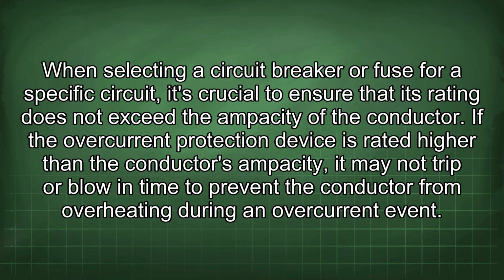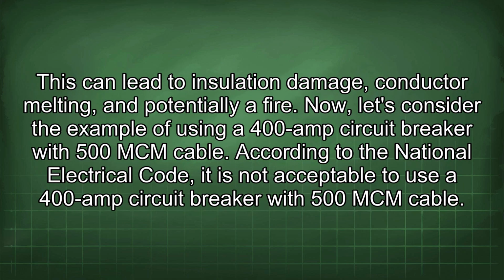If the overcurrent protection device is rated higher than the conductor's ampacity, it may not trip or blow in time to prevent the conductor from overheating during an overcurrent event. This can lead to insulation damage, conductor melting, and potentially a fire.